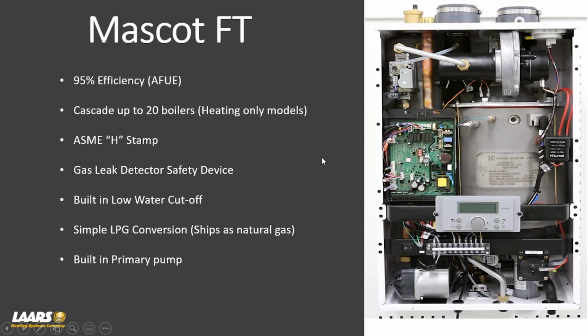Very simple. We have a built-in primary pump. So when we talk about primary, secondary, and a boiler pump, that's built right in the cabinet. We also have inlet domestic and hydronic screens. So on the heat only, you're only going to have a hydronic screen. But on the domestic side, you'll have a domestic strainer as well for the combi boilers. And those are held in the bottom part of the cabinet. A little cotter pin, you remove the cotter pin, pull the strainer out, and you can clean it.